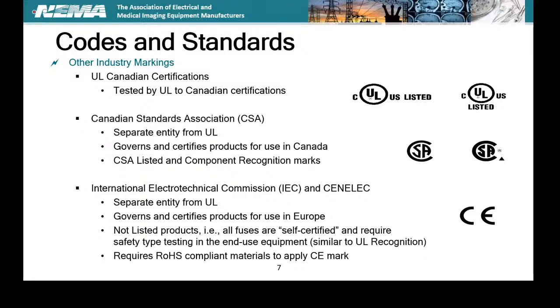But in chapter 1, we put some information in there that says the products that you're installing need to be designed and listed to be compatible and developed in combination with the National Electrical Code. Because a lot of these European type standard products have different bending radiuses. They won't have enough room to give you the bending radius in your conductors. When you start getting into those assemblies, you'll recognize that some of that equipment is much smaller. You take an IEC rated starter and compare that to a NEMA rated starter. There's a big size difference between those two for the exact same type of motor load. So those products are designed not with an eye on our installation requirements. You've got to be very careful when you have something that's CE marked and doesn't have a UL or some other type of equivalent listing recognition.